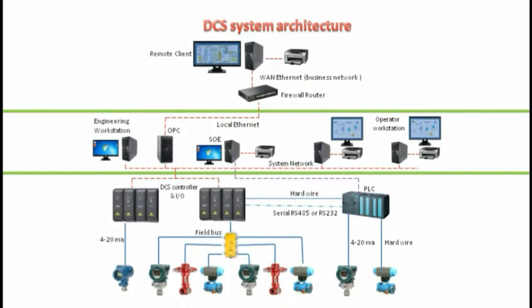Here we go to a more detailed system architecture. This can be applicable to any DCS system depending on the design; this setup is just to demonstrate the main elements. Some variations should be expected from system to system. The DCS controllers are a redundant set, meaning if the primary controller fails, the secondary one will take control. The redundancy might also be applied to the IO levels if required, or a mix of redundant and single IOs depending on the design and requirement.